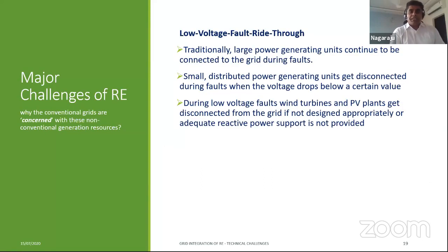Another aspect we looked at is the low voltage fault ride through. I think I explained this already. Conventional machines have been helping the grids to ride through the faults by not getting disconnected. Traditionally, the small distributed generators have been allowed to get disconnected when there is a fault or when the voltage is pretty low. Usually ROCOF relays are set on the distributed generators, so when the rate of change of frequency goes above a certain value, they get tripped. But that's not going to be the case in the future. It's already not the case in the UK. Even these distributed generators have to stay connected during the faults.